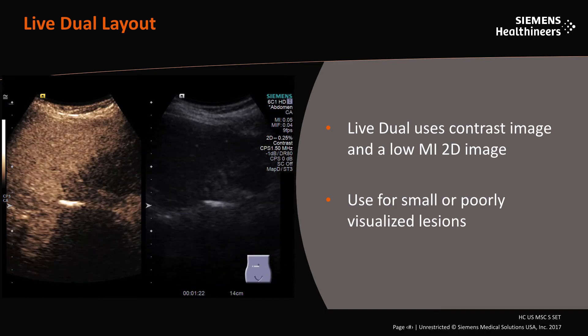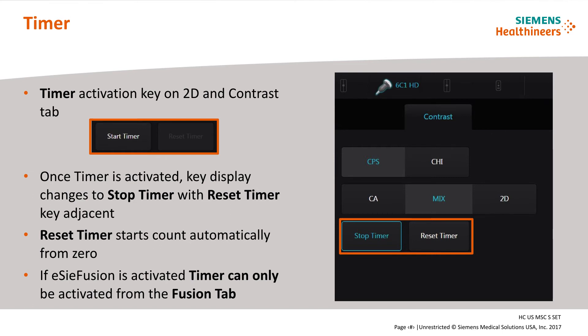The timer control key is located on both the 2D and contrast tabs. To activate, select start timer — the display will change to stop timer, and the reset timer key will illuminate beside it. To stop the timer, select stop timer; the time clock will remain on the image screen and display the stop time. Selecting reset timer will set the timer back to zero and automatically start the active time clock count again. Use the reset timer for continuous flow state contrast exams to time and view contrast reperfusion in a region of interest. Note that if eSieFusion is activated, the timer can only be activated from the fusion tab.